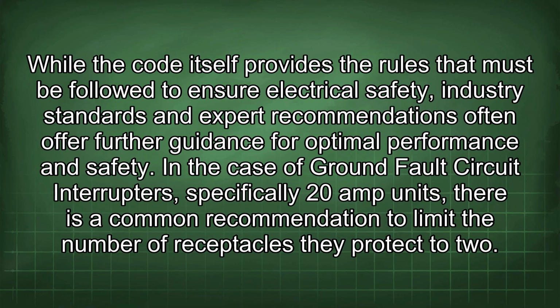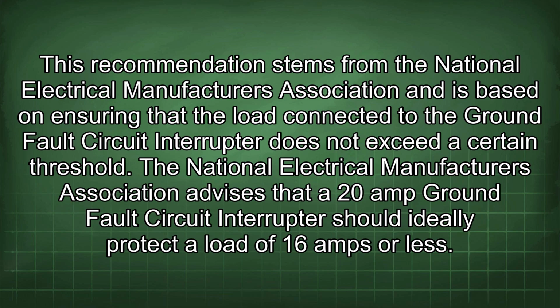While the code itself provides the rules that must be followed to ensure electrical safety, industry standards and expert recommendations often offer further guidance for optimal performance and safety. In the case of ground fault circuit interrupters, specifically 20-amp units, there is a common recommendation to limit the number of receptacles they protect to 2. This recommendation stems from the National Electrical Manufacturers Association and is based on ensuring that the load connected to the ground fault circuit interrupter does not exceed a certain threshold.